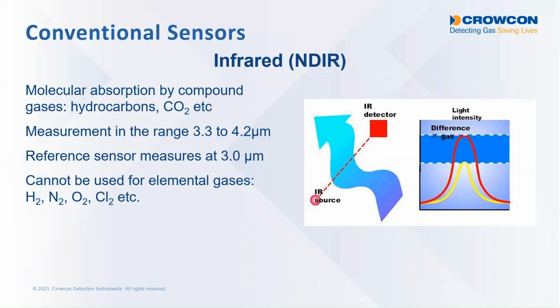It works by using two sensors that are looking at infrared energy at wavelengths that will be absorbed by hydrocarbon or carbon dioxide gases. For hydrocarbons, absorption happens at a 3.3 micron wavelength. For CO2 measurement, absorption happens at 4.2 micron wavelength. So the very finely tuned infrared sensor can measure a reduction in infrared energy at those specific wavelengths to determine the presence of gas.